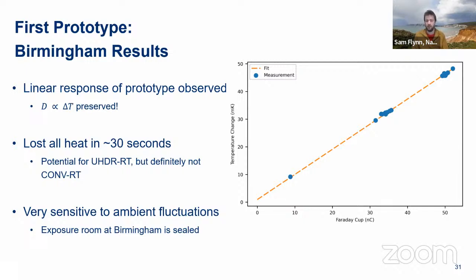Radiation-induced heat is lost in 30 seconds, so there's no way you could use this for conventional therapy. If your beam is getting close to a duration of 30 seconds, you're not going to get anything useful from this. And it was very sensitive to ambient fluctuations. The exposure room at Birmingham was very nice and very sealed. There's no air conditioning in there, so it is almost the best case for doing this kind of measurement. It doesn't really replicate clinical use. But we're not dissuaded by this. We still wanted to see where we could go with calorimetry.